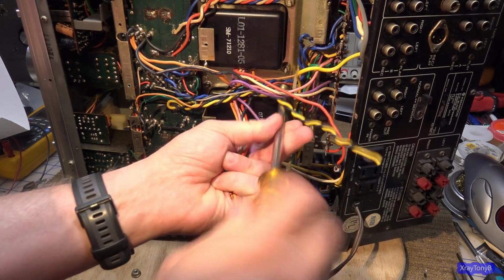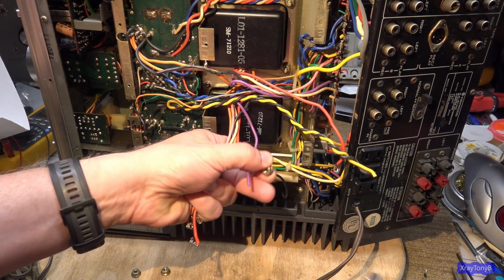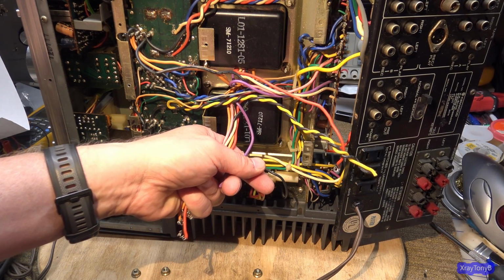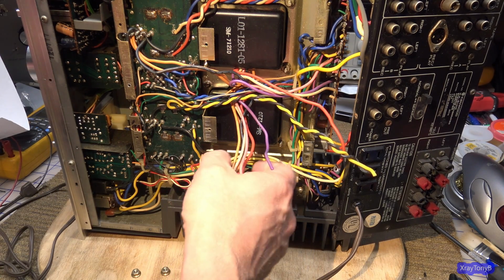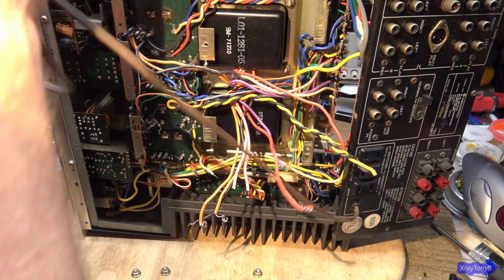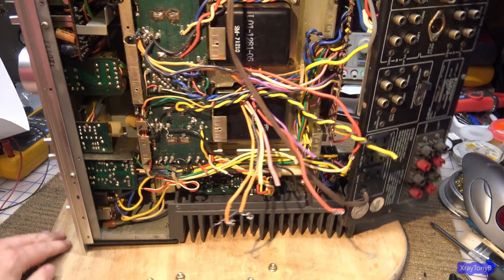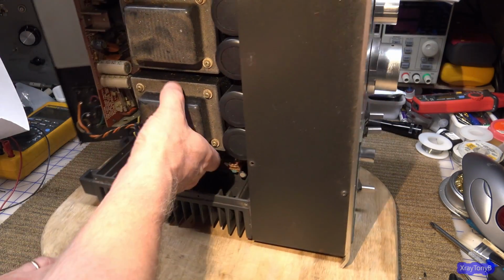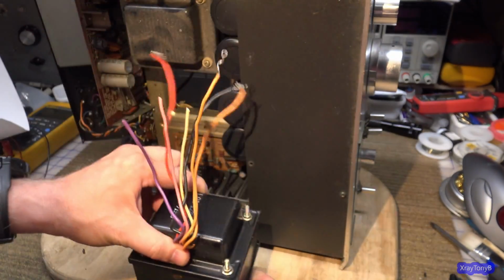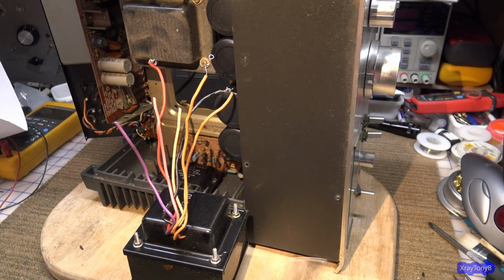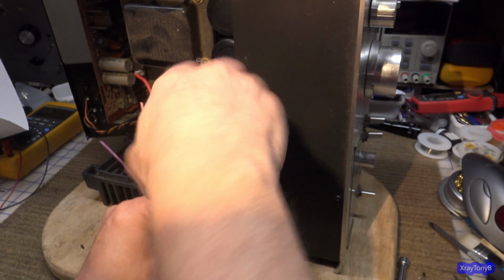Now, again, if the fuse opened up because the transformer was grossly overheated, there's a good possibility that the enamel on the windings has been damaged and burned. And even though the fuse opened up, the transformer itself would still be bad and need to be replaced. But hopefully all that happened was an overcurrent situation. I mean, that's a huge transformer for just a single 90-watt amplifier, a mono amplifier. So hopefully that's a different size. So let's see here if I have the other one that goes on there. If that's 7mm, yep. And hopefully this is all there is to it.